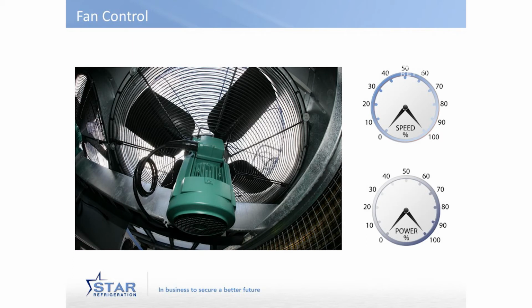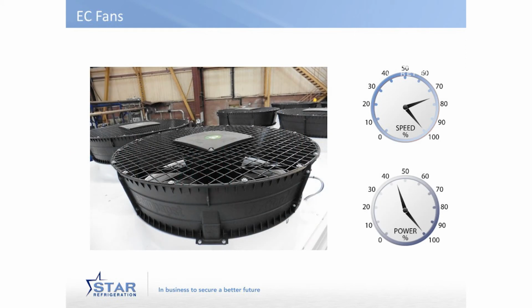If we manage to back off the speeds by using a variable speed fan, and there are lots of them available in the market now, you don't need to buy a separate drive. You can actually have the variable speed built into the fan. If we drop to 75% speed, the fan will still deliver 75% of the airflow, but we only consume about 41% of the power. And if we take it even further and reduce the speed down to 50%, we'll only be consuming 12% of the power. The same goes for variable speed on pumps.